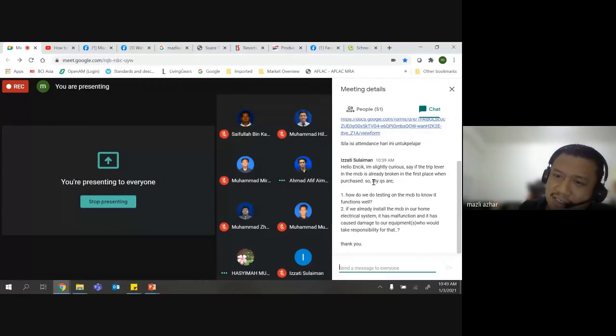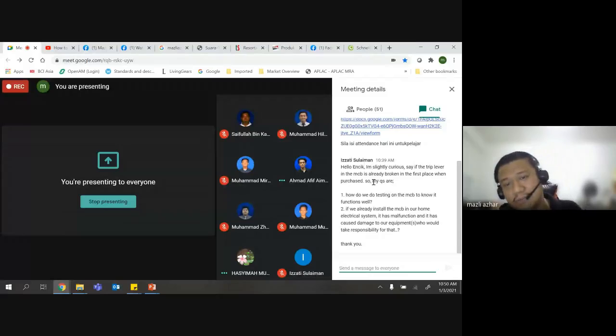Okay, if the MCB trip lever is already broken in the first place when purchased, the first thing you need to do is change it directly. The function of the trip lever is to turn the breaker on and off. But let's say you are in the middle of the night, there's no store open, and you still need to ensure that it still functions, then you can force it to turn on, and you can see the lever is in the on position at the top. Normally it's simple: when the lever is at the bottom it is off, when the lever is on the top it is on. And then, what other things you can do, you can use a multimeter from the top and bottom to ensure that there is continuity at the breaker itself. Because I believe, Izati, you have no issue because you're an electrical student, right? You will know how to use a multimeter.